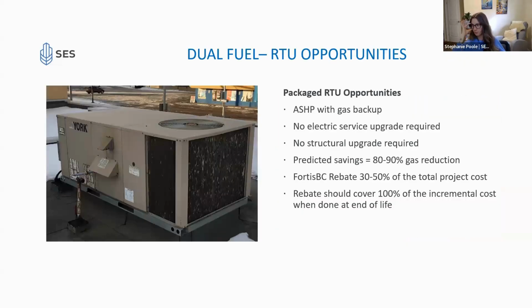Next slide. So the opportunity here is, I can't go full electrification. I've tried it. I don't have electrical capacity. So I'm going to go with an air source heat pump with gas backup. And typically you can do these with no electrical service upgrade. Almost always you could do it with no service upgrade if they already have cooling. If they don't already have cooling, it's a bit more of a maybe, but still possible depending on the building.